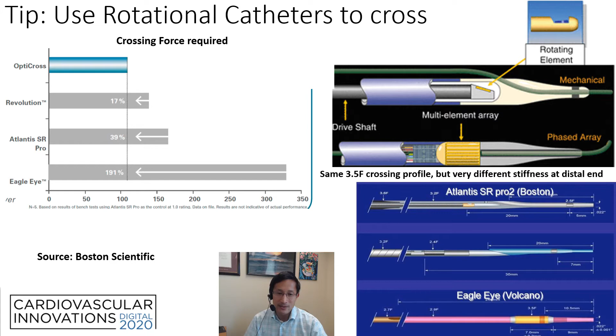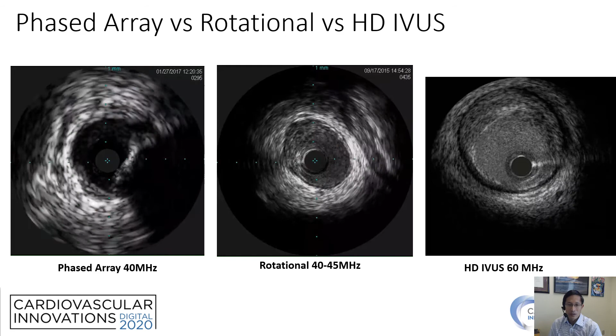Rotational catheters also have the benefit of having improved image quality. So on the left, you see the phased array catheter, which has 40 megahertz, whereas in the middle, you have the rotational catheter, which is also at 45 megahertz and has a much higher image quality. The HD IVUS at 60 megahertz on the right invariably is rotational and has the highest quality image, which is getting almost equivalent to OCT.